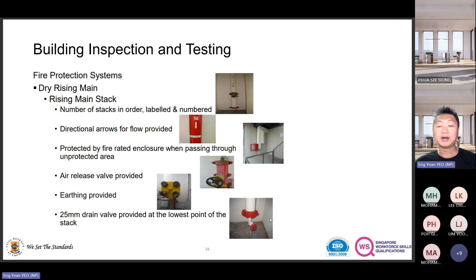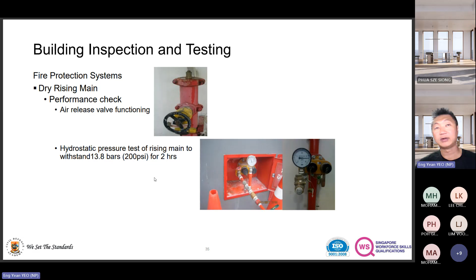They said there was a fire cert inspection, where they test the dry riser by putting water inside and measuring whether it reaches 200 psi. When the riser is filled with water, you need to drain it off. That's why these drain valves are there, to make sure you can drain off all the water. That applies to dry risers for low rise buildings, especially basement car parks. For the performance check, make sure the air releasing valve is functioning. When you press it, you see the air escaping. The hydrostatic test is to make sure you reach 200 psi for at least 2 hours. What they test is the integrity of the piping wall. Does it give way? If it does, something is very serious, perhaps through wear and tear, and that's where you need to know. We need to repair that particular section of the dry riser.